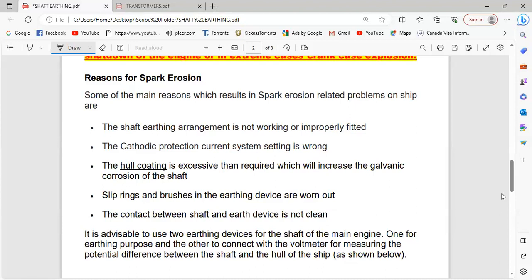Okay, so why will we get the pitting or spark erosion as it is called? Shaft earthing arrangement is not working properly, as I mentioned, on one of my ships that happened, and that is why they ran into such huge problems. Okay, although the brushes were in place, they had worn down quite a bit. And if they wear down quite a bit, despite putting it even on the third setting, it is not going to be pressing against that particular ring, the slip ring. Okay. Cathodic protection current is wrong.